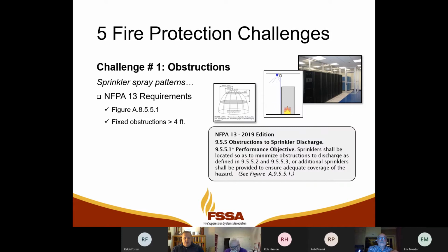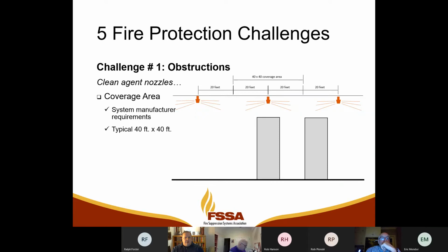For spray patterns, we're typically designing these systems to NFPA 13, but when these systems get installed without regard to the sprinkler locations, we can break some of the NFPA 13 rules for obstructions. The code is going to wind up saying we have to make accommodations for this. We either have to move the sprinklers or not install the partitions. There are different ideas for that. Nozzle coverage on clean agent nozzles can also be impacted when adding these things. We worry about gas being able to get to these new volumes that the aisle containment systems can create.